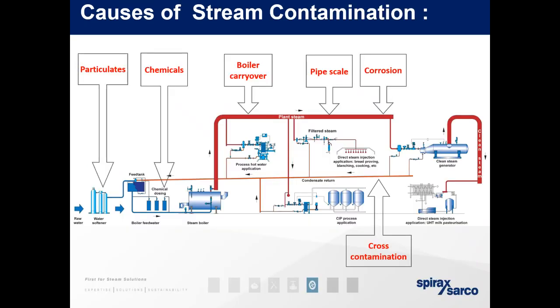So causes of steam contamination. As you can see on the screen, we have a kind of mini whole system. It starts when you enter your raw water into your softeners. So you get particulates there from the tap water. It could be parts from their line. It could be salts. It could be various different minerals. So we try to filter those out. You then get chemicals that you have to dose into your feed tank. Again, this is a contaminant into the water.